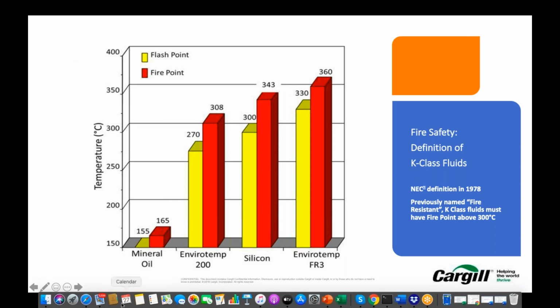So this higher fire point doesn't mean it is much superior to the other fluids as far as fire safety is concerned, but it is superior in terms of handling. When it comes to shop floor handling or transformer manufacturing, there are chances that you may end up with some impurities while processing the transformer, and the superior fire point helps to overcome those impurities. So even though you get a compromise on the fire point during manufacturing, from 360 to 350 or 340, your transformer is still K-class, equally fire safe, whereas in the case of other technologies, that cushion goes away. That's the reason you get a slightly better advantage during the manufacturing and processing of the transformer when you are using natural ester. Next.